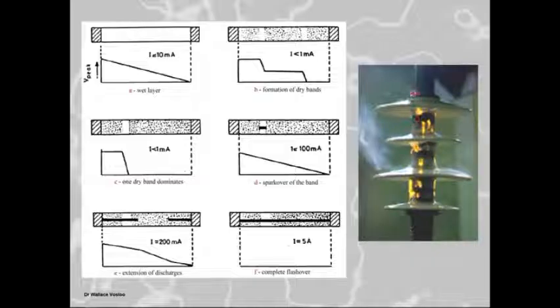And so the current that's flowing through here is very much the driver of how close you are to arcing, because when it is dry band discharges in the form of little corona discharges and so on, the current levels are under a milliamp. When you start looking at dry band discharges and you're looking at sparking, corona, you'll hear that and you smell ozone, okay? And it's a sweet smell. Very nice, actually. I love it.